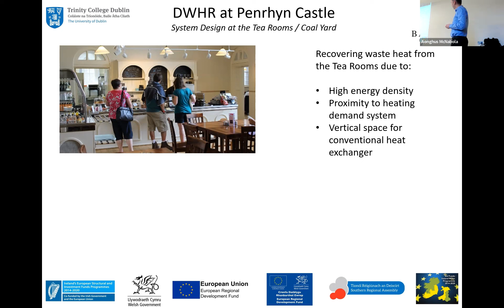So when you see the system, where we recover the heat is maybe three or four meters away from where we put it back into the castle. In some places, hotels and businesses, the distance between those two could be far apart, which wouldn't necessarily make it unviable, but would reduce the viability. We also had a vertical space constraint for the type of heat exchanger we were using.